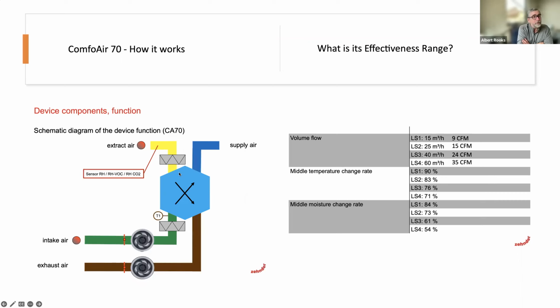But right now it's just pulling from that same room into the yellow. It's going across the core, doing the heat exchange at roughly 85%, giving it to the brown line, and the brown line, the fan is pulling it and sending it back outside, right? So that's a classic HRV. And when we look at how it works, it's just going to be one hole in the wall. We set it up, we turn it on, it runs all the time, and there we go.